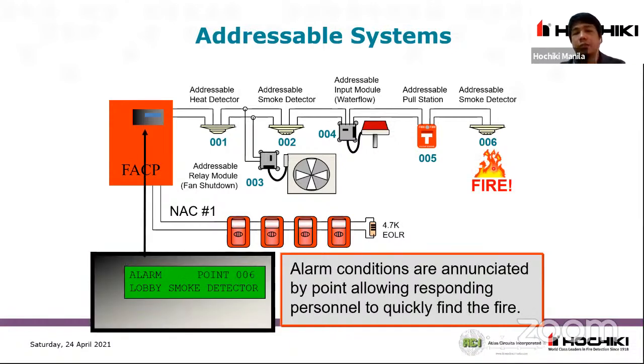Okay? So in terms of fire, alarm conditions are annunciated by point, allowing responding personnel to quickly find the fire. So unlike doon sa conventional system natin, dito sa addressable, kapag nagkaroon ng detection dito sa address 6, makikita natin sa panel natin na address 6. So as much as possible, nilalagyan natin ng location text. So specific dapat yung location text natin para mas madali siyang ma-pinpoint. So ayan, nakalagay lobby smoke detector. So mas mabilis niyong mapupuntahan yung addressable device na nagkaroon ng alarm para ma-check. In comparison with the conventional devices, hindi nyo makikita kagad yung specific na device doon sa panel.